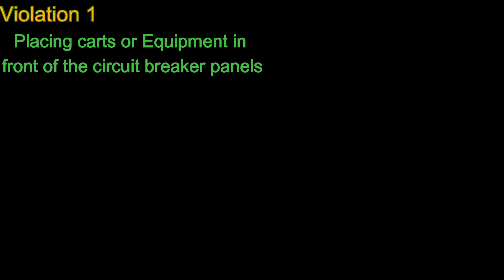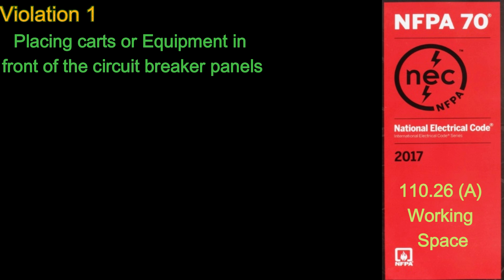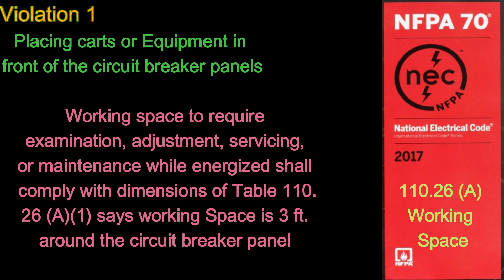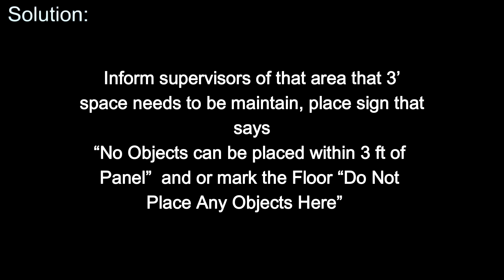Finally, Number 1: Placing carts or equipment in front of circuit breaker panels. Code NFPA 70 110.26 A — working space. Working space required for examination, adjustment, servicing, or maintenance while energized shall comply with the dimensions of Table 110.26 A.1, which states working space is three feet around the circuit breaker panel. Solution: Inform supervisors of that area that three feet of space needs to be maintained. Place a sign stating no objects can be placed within three feet of the panel, and mark the floor accordingly.